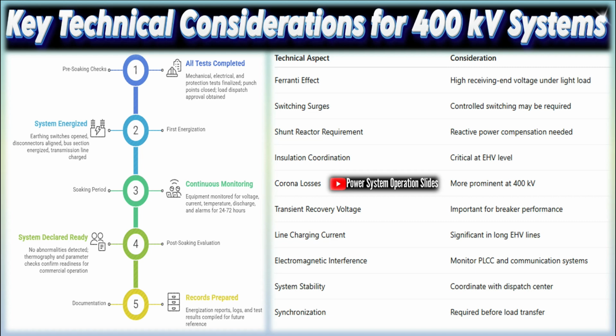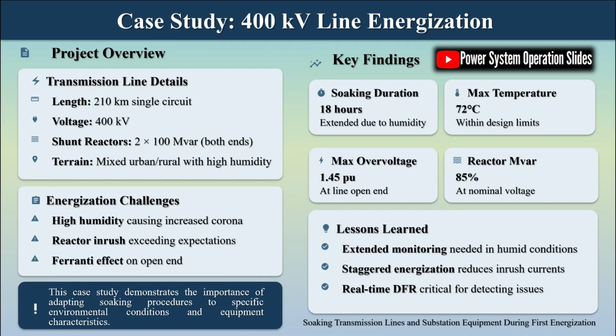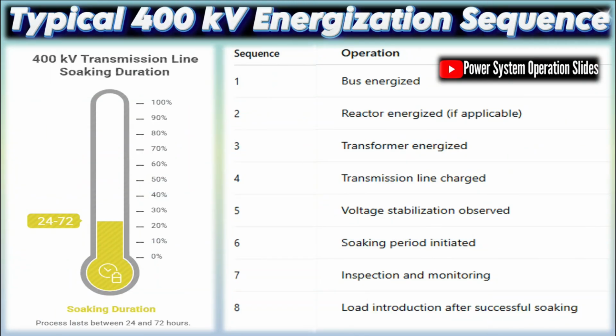Monitoring activities performed during soaking are equally important as the energization process itself. Engineers continuously observe leakage currents, temperature variations, partial discharge levels, transformer oil parameters, and equipment operating conditions. Any unusual trend may indicate the presence of insulation defects, contamination, loose connections, manufacturing flaws, or installation issues.